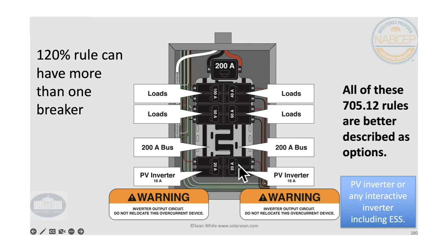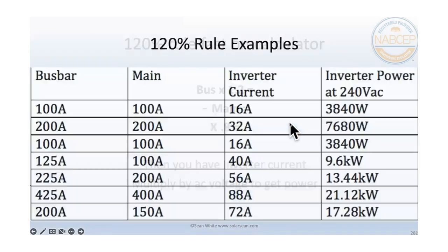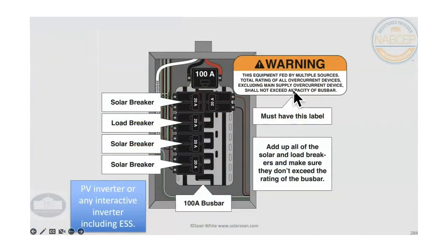We can put multiple breakers as long as they don't add up to 125% of the inverter current being more than 20% of the bus bar if the main breaker was equal to the bus bar. Another thing to look for is if the bus bar is, say, 225 amps, that's a big bonus because you get 120% of 225 amps, and that gives you a lot more options. We're going to look at some neat things coming up here pretty soon. This is something that can oftentimes be used if we just read the sticker: equipment fed by multiple sources, total rating of all overcurrent devices, excluding the main, shall not exceed the ampacity of the bus bar. So that just explains what that is.